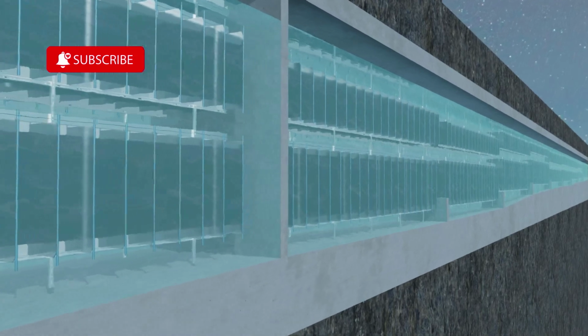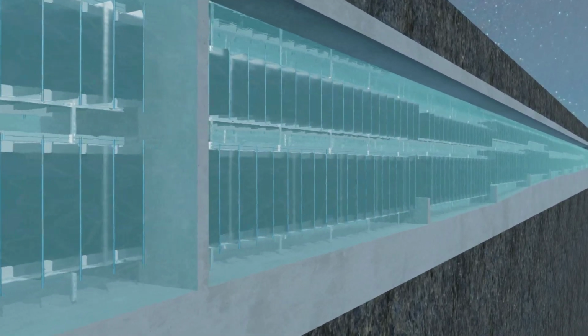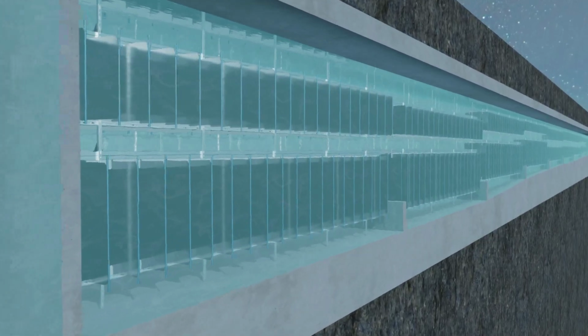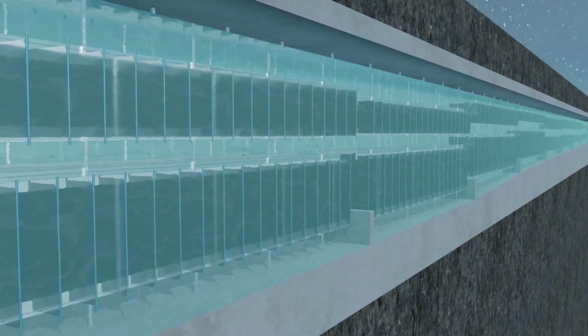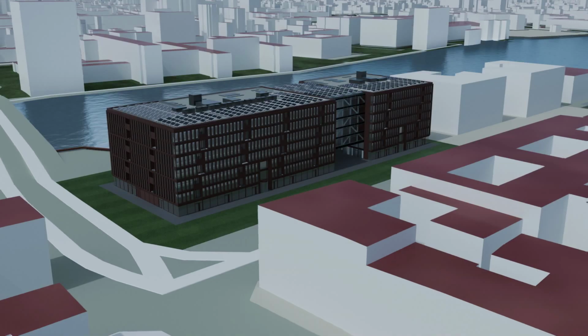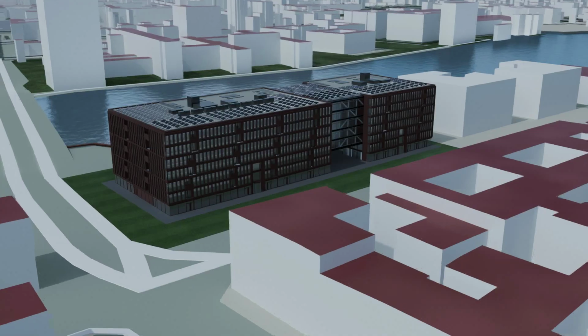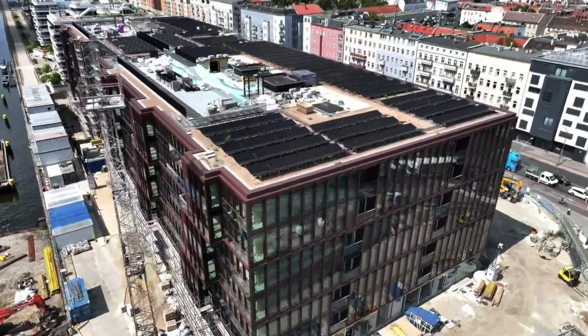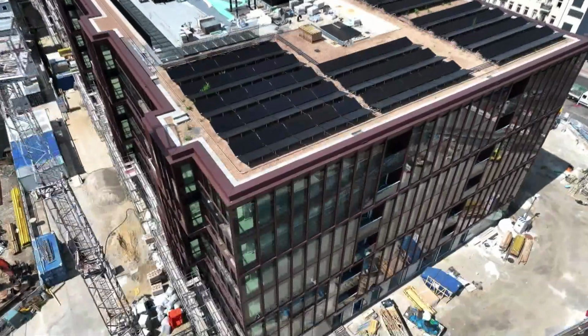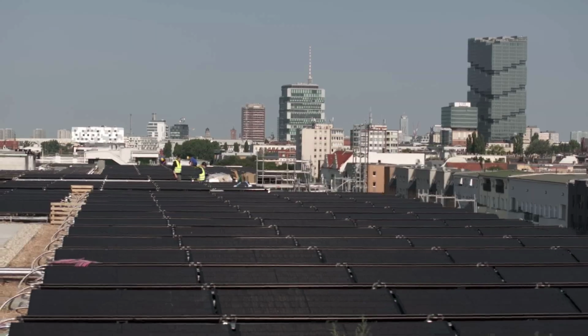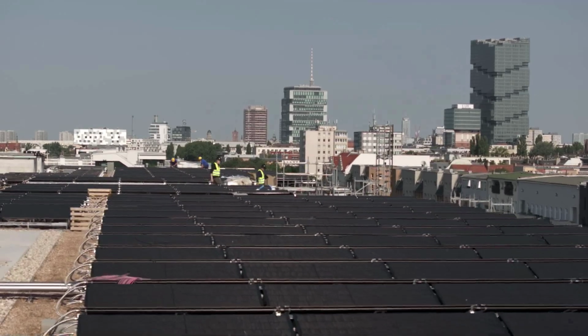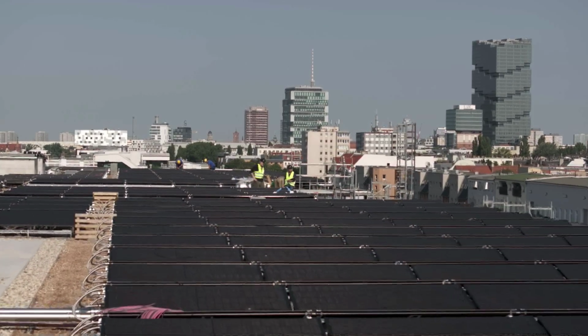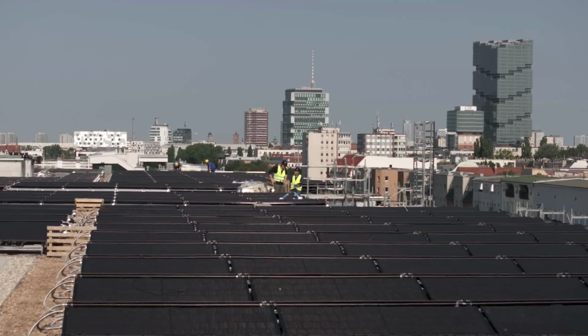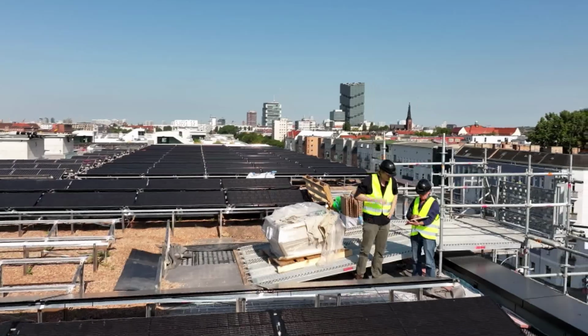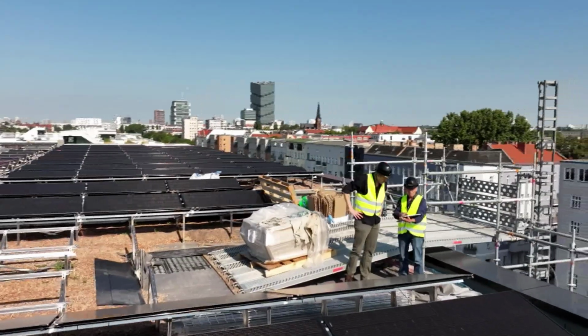The large water tank serves as an intermediate storage tank for the heat. By the start of the heating period, the water in the tank will have warmed up to a maximum of 25 degrees Celsius. And the annual heating and cooling cycle starts all over again. Thanks to efficient management of the large water and ice storage tank, it is possible to produce around 7.5 kilowatt hours of cooling from the 1 kilowatt hour of electricity consumed by the heat pumps over the course of the year. This means that not only the heating, but also the cooling of the building is very efficient.